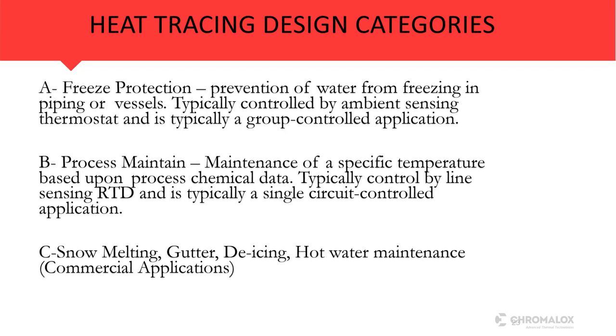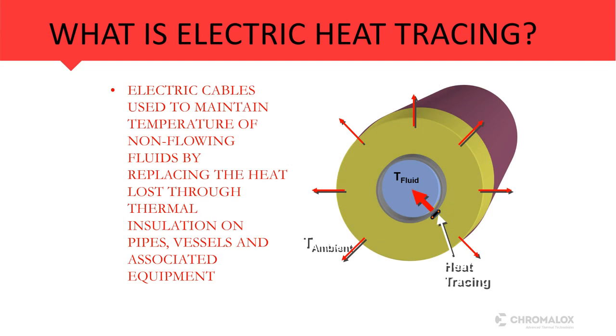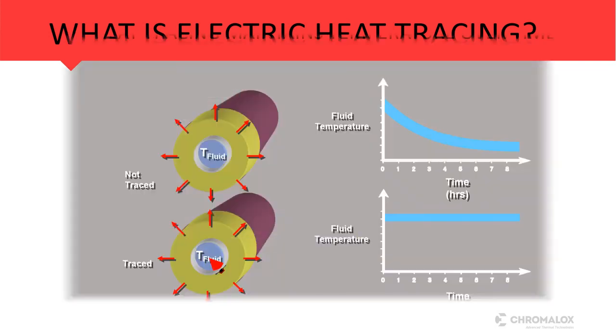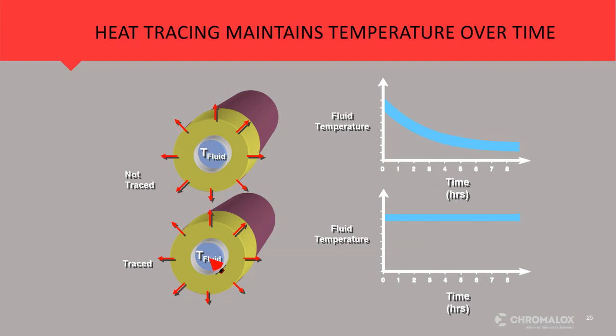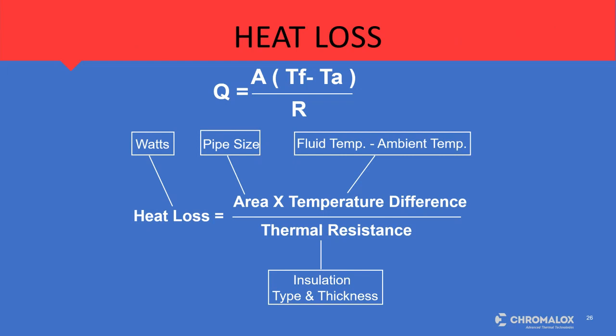What is heat tracing? Most of you may or may not be aware, but heat tracing is used to maintain the temperature in a non-flowing condition. So we basically need to understand that we can't heat up a line or a vessel unless it's non-flowing. If we look at a line that has no heat tracing on it, just insulation, over time it's going to seek some temperature, it's going to get to some equilibrium, and it's going to stay there. What we need to do is put back that heat loss, and that's what heat tracing does, right? It's going to give us back that heat loss that we need, and then we're going to maintain the temperature that we're looking for over a specific period of time.